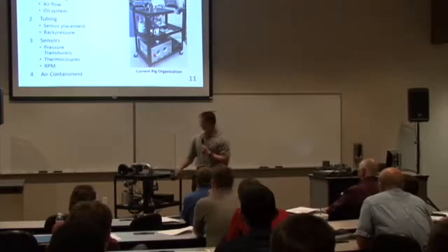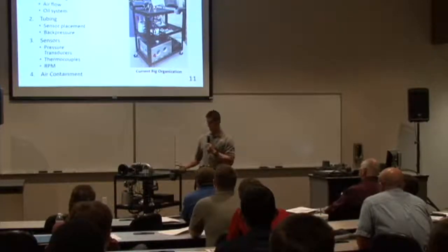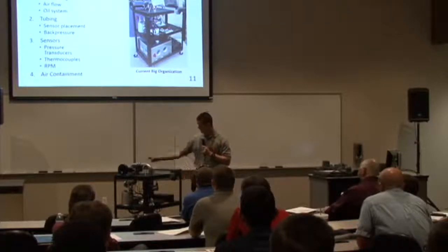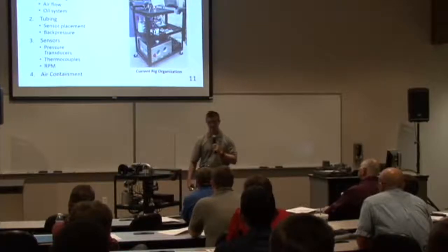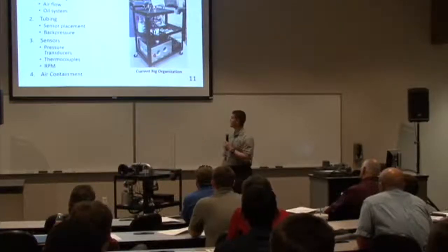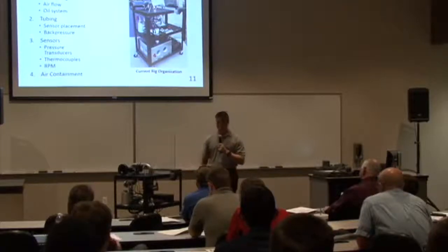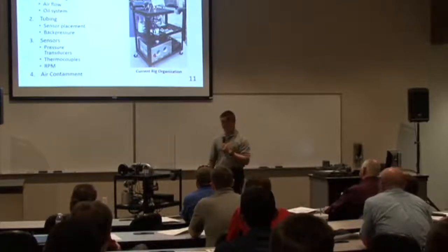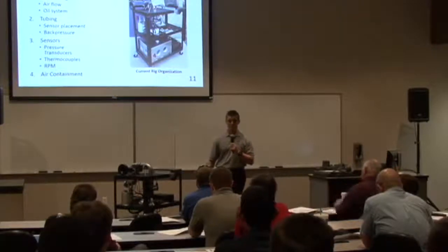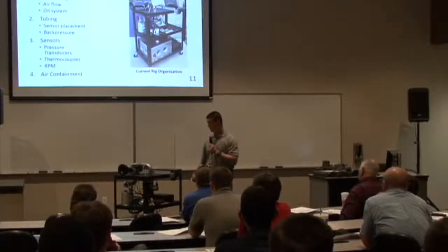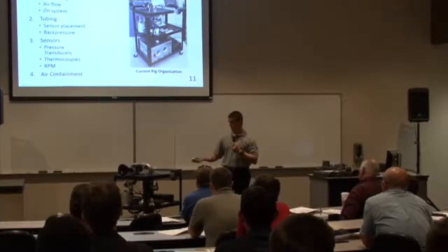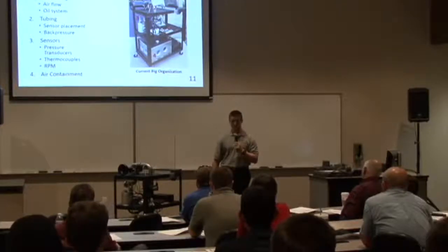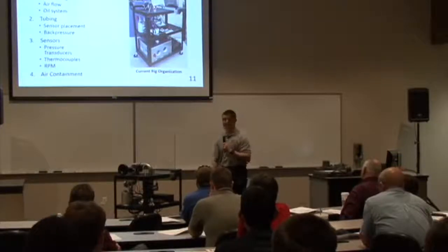Connected to that is our airflow system, taking compressed air in from the wind tunnel air compressor, as well as our oil system, which lubricates and keeps the bearings at a constant temperature. Second, we have our tubing, which allows us to create back pressure on the compressor side and houses all of our instrumentation - our 8 pressure transducers, 8 thermocouples, and finally our speed sensor on the compressor housing itself.